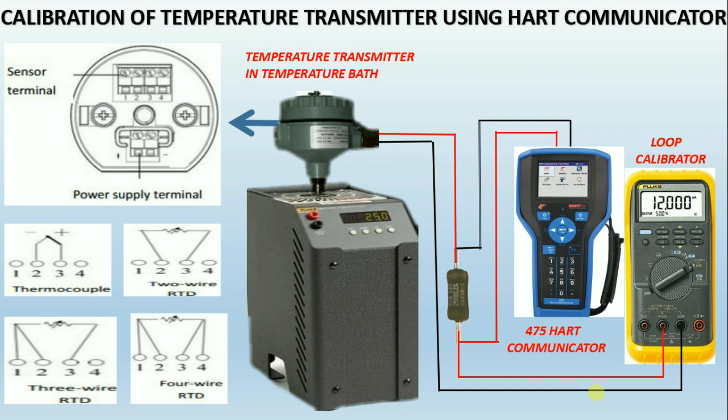After completing the connection, set the zero temperature value in the calibration bath according to the lower range value in HART, and check the corresponding 4 milliamps in the loop calibrator. If it is not showing the corresponding milliamps, then using HART do the lower sensor trim.